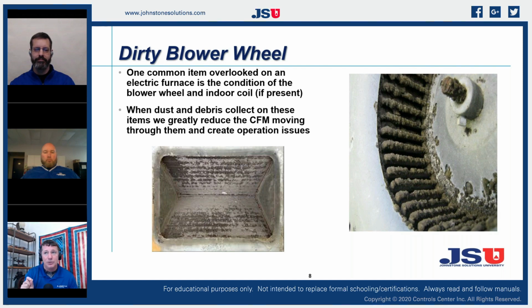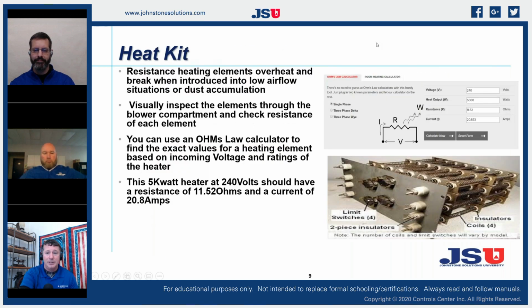So those numbers, that temperature rise and verifying the CFM, is going to tell us what our motor is actually doing. And the number one culprit of motor failures is failed airflow, because we didn't do our job, right? That motor is trying to get that air to move, but if it has a packed up fan wheel, which has a cup to it, it can't move the air. If it has a dirty coil, it can't move the air. So we have to be able to check these things, and it's overlooked, pretty common in our industry.